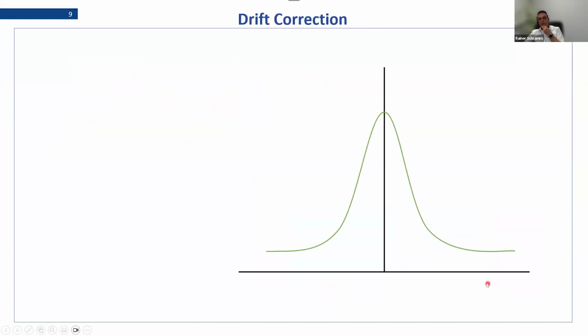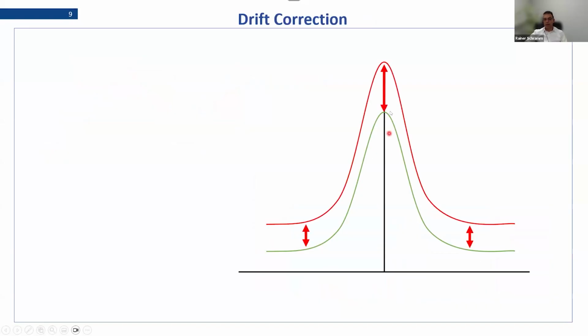Okay, but what does drift correction mean? What is changing over time? It means that the intensity of our line could be higher or lower, and the background could also change. And of course, both could change in a different way. Here you get a kind of slope, and here it's just the intensity which changes. And the reason for this is, for example, the peak positioning I told you about already, so that if you don't do your MCA and your line positioning correctly, then your system is very sensitive to any movements.